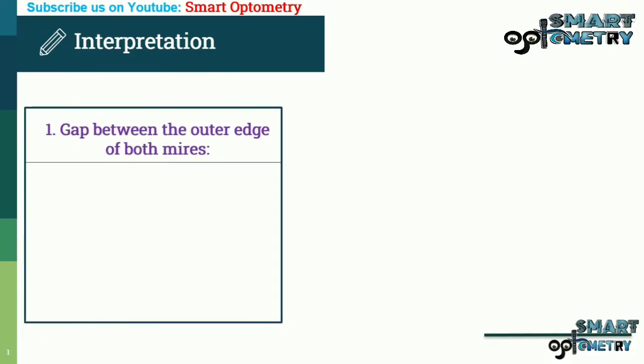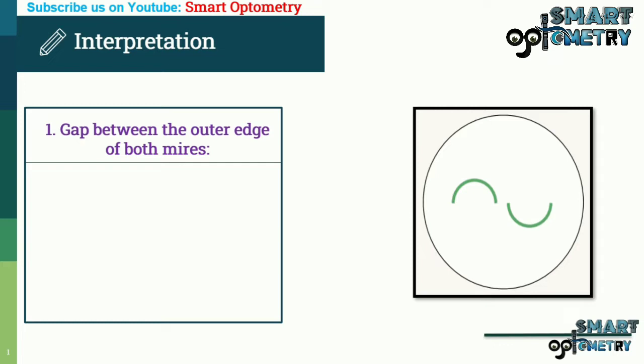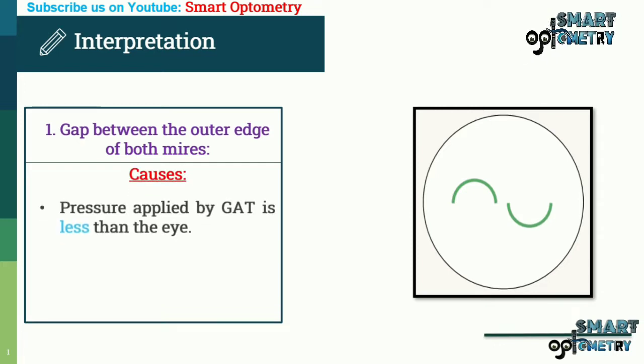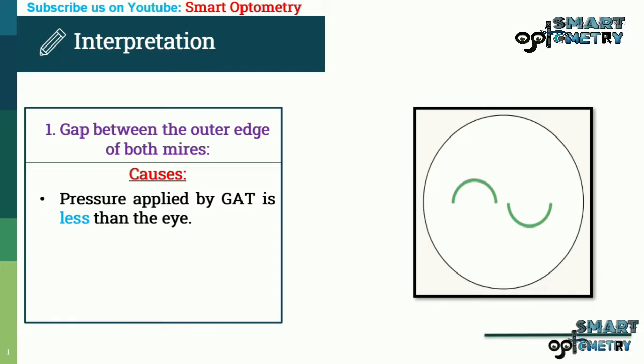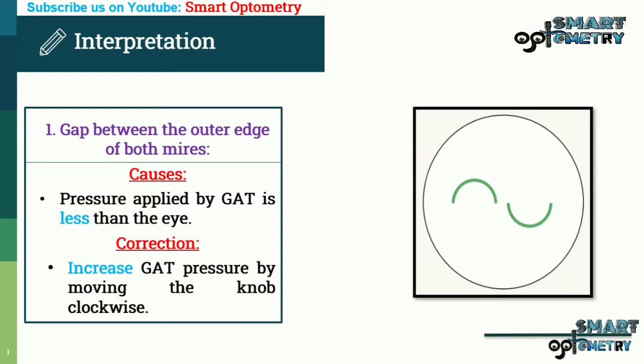Interpretation: Gap between the outer edge of both mires. This occurs because the pressure applied by GAT is less than the eye. Correction is to increase GAT pressure by moving the knob clockwise.